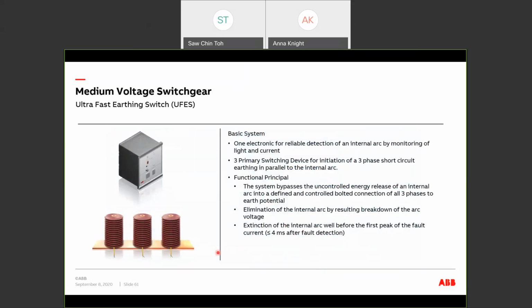What is an ultra-fast earthing switch? This system consists of one electronic controller and three primary switching devices. The controller will detect an internal arc by monitoring the light and current flowing through the switchboard, and upon detection of the internal arc, the controller will signal the switching device, initiating a three-phase short circuit to earth in parallel to the internal arc. By redirecting the energy flow, we can extinguish the internal arc within 4 milliseconds, well before the first peak of the fault current.